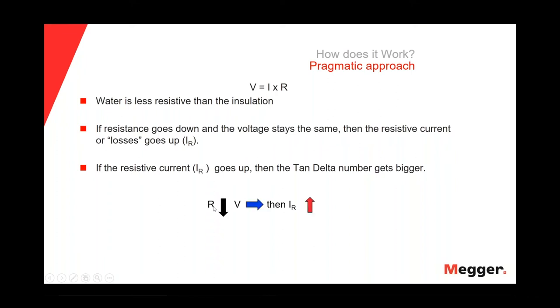Once again, if the resistance goes down and the voltage stays the same, then the resistive current will go up. And if the resistive current goes up, then the tan delta goes up. And we can see very easily from this equation, one more time, if the resistive current goes up, the tan delta test will go up. If the resistive current goes down, then the tan delta goes down.